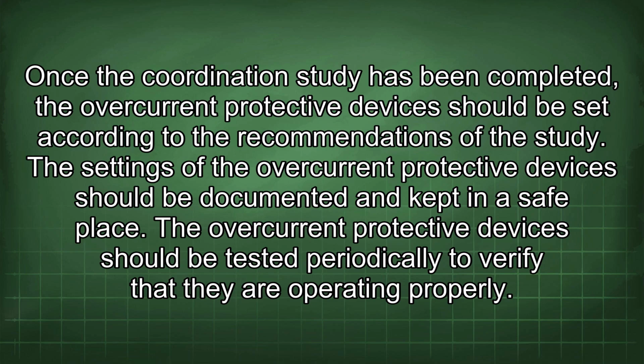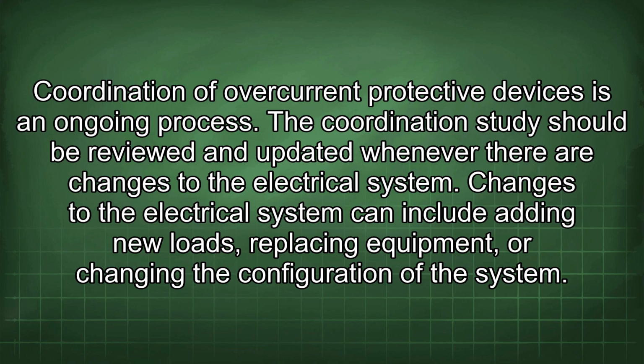Once the coordination study has been completed, the overcurrent protective devices should be set according to the recommendations of the study. The settings of the overcurrent protective devices should be documented and kept in a safe place. The overcurrent protective devices should be tested periodically to verify that they are operating properly. Coordination of overcurrent protective devices is an ongoing process. The coordination study should be reviewed and updated whenever there are changes to the electrical system. Changes to the electrical system can include adding new loads, replacing equipment, or changing the configuration of the system.